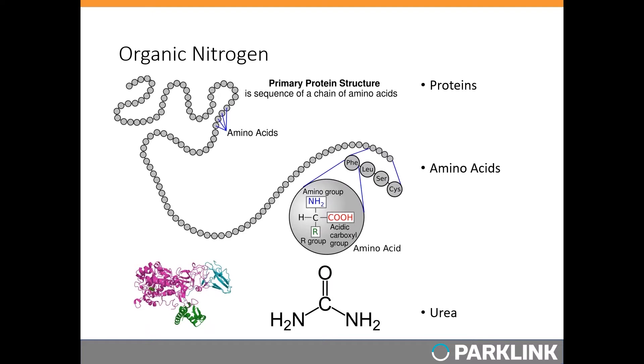Organic nitrogen mostly comes in through the influent in three forms: proteins, free amino acids, and urea. Proteins are long chains of amino acids, and the amino group is the nitrogen-containing group of amino acids. As these organic nitrogen compounds are converted in the wastewater treatment process, the nitrogen bound in proteins mostly gets released and becomes part of the nitrification process. Some small amount of organic nitrogen — particularly from meat processing or dairy plants — may never be released. The biggest nitrogen contributor to municipal influent is generally urea, released via the urease enzyme.